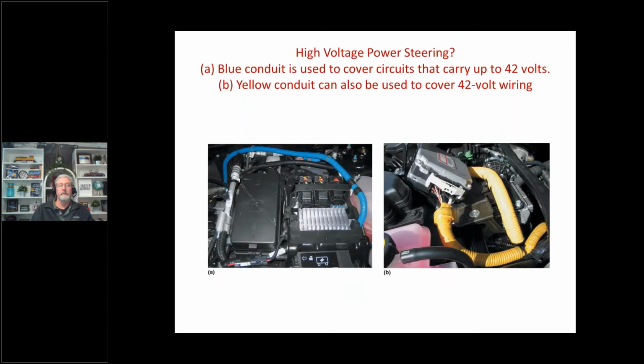Be aware that some of these may be higher than 12 volts. In this case, with blue conduit and yellow conduit on the cables, that can be as high as 42 volts. So we want to be careful - 36 to 42 is your typical voltage on those cables.